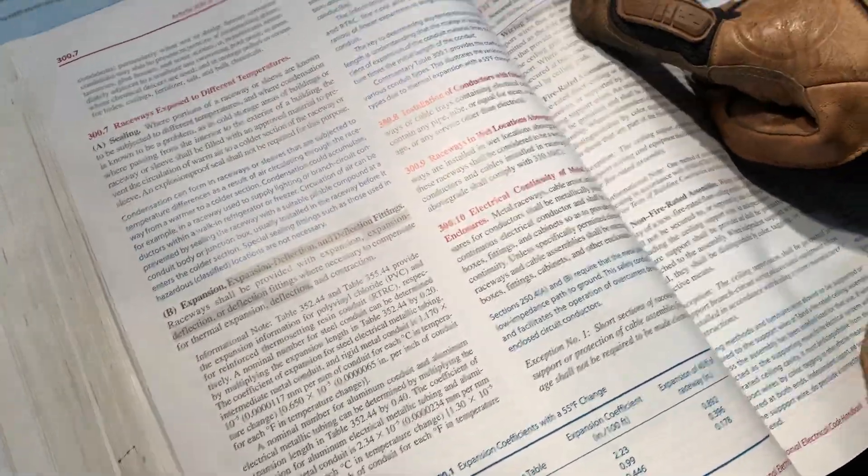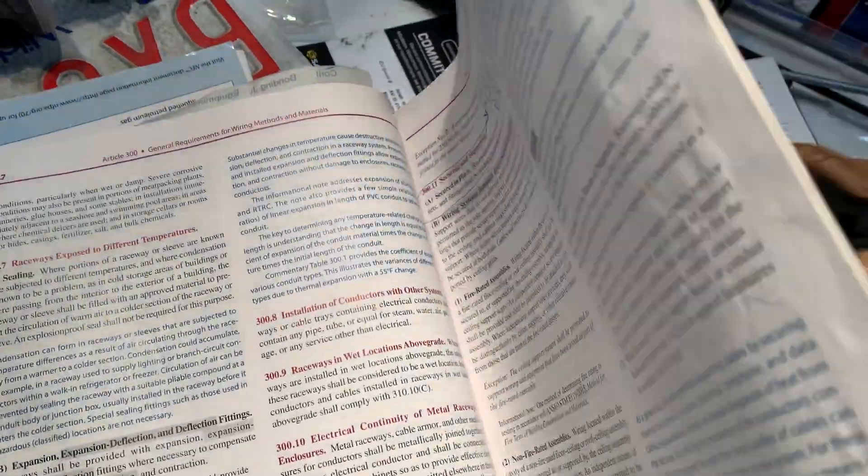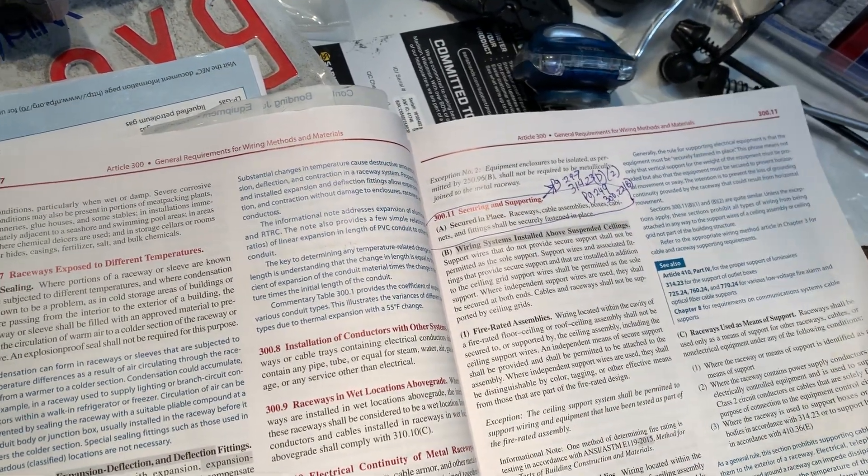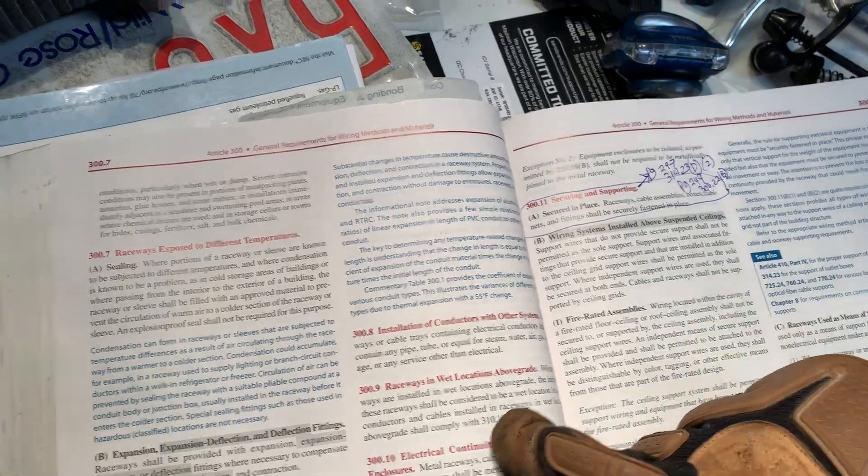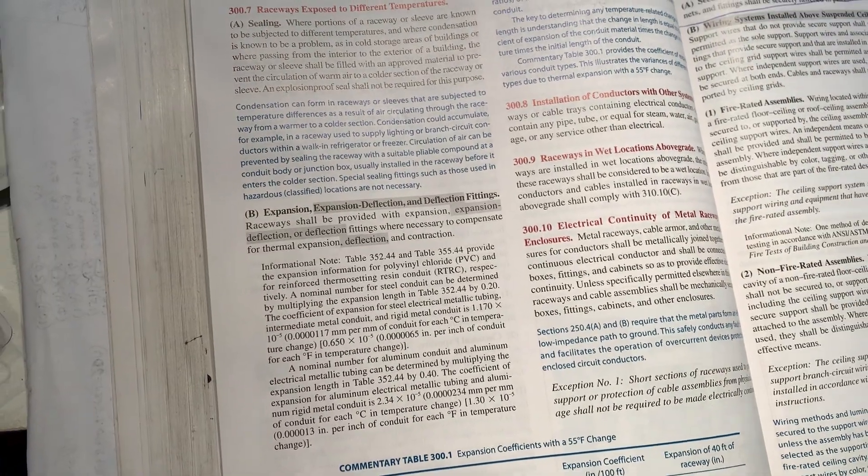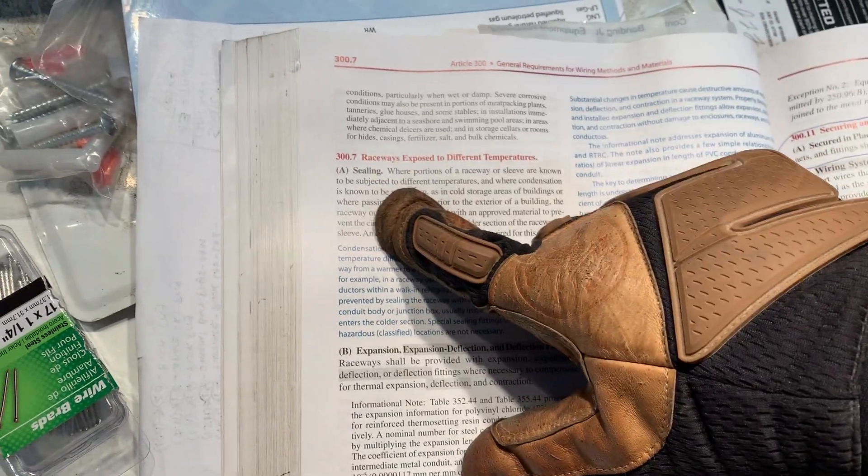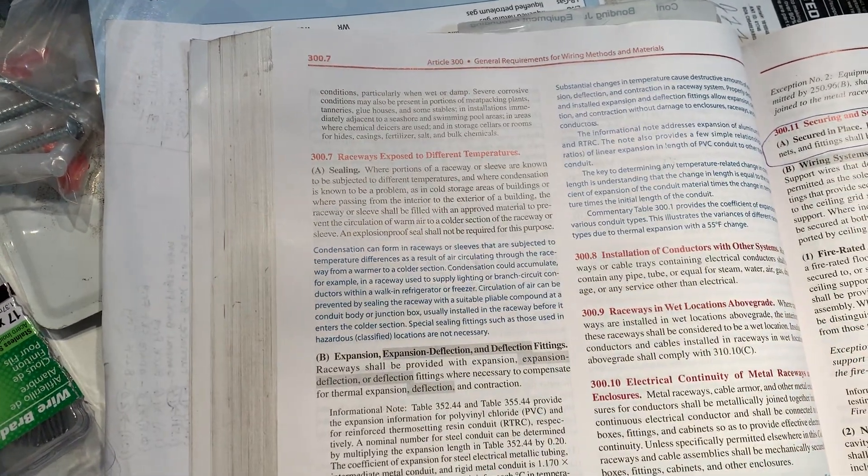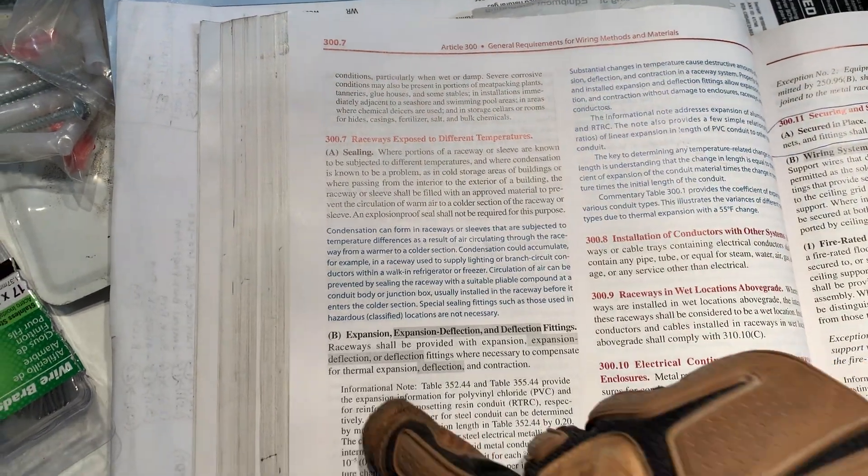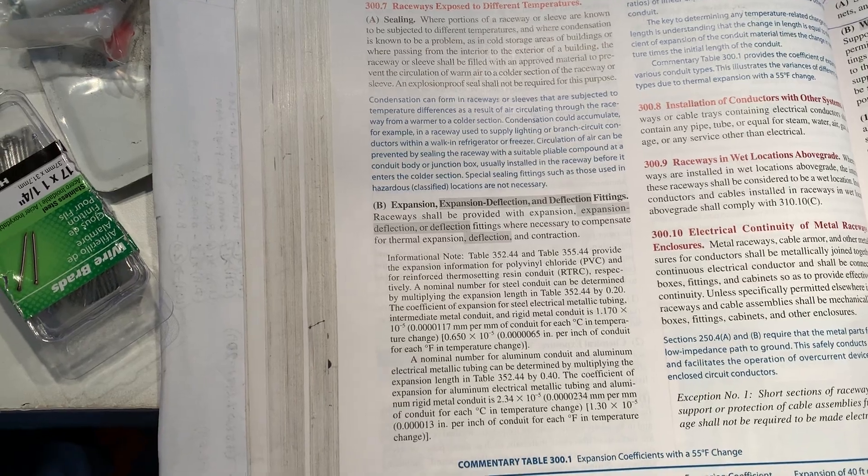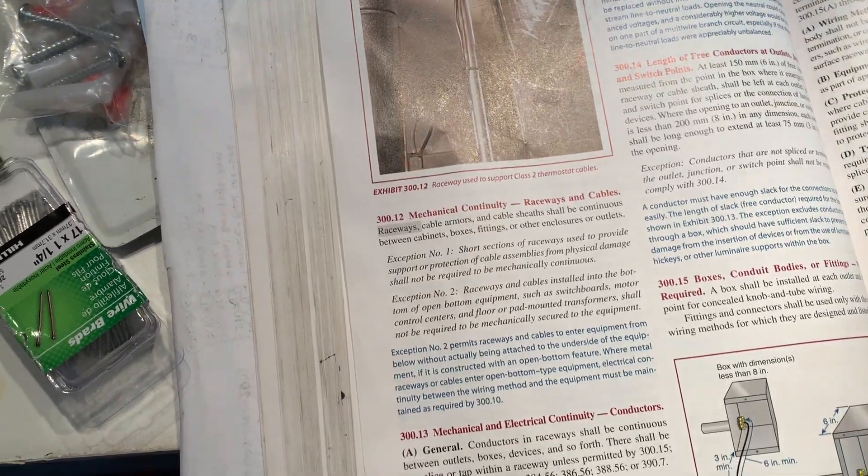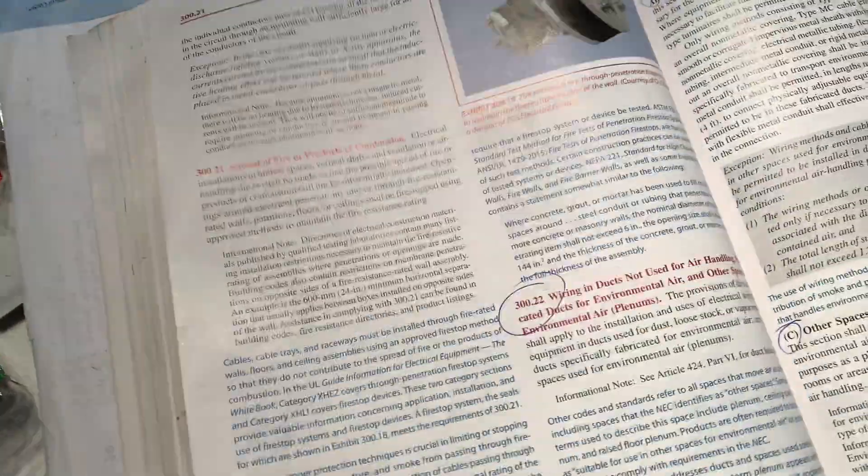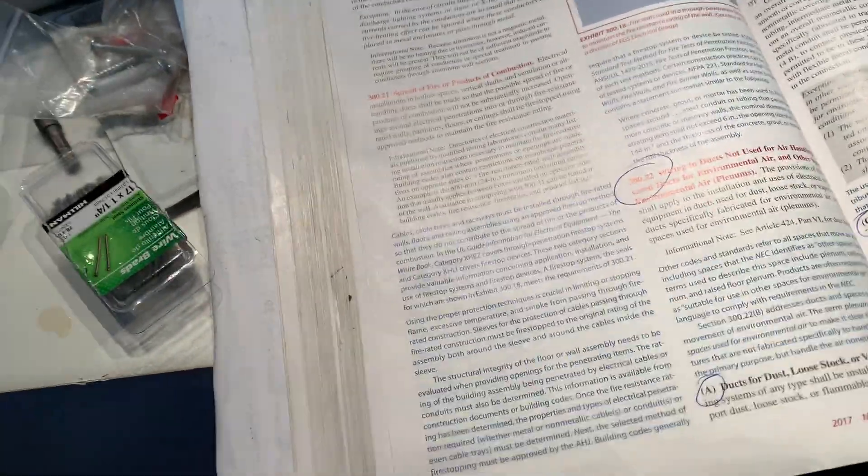Securing and supporting your straps and raceways. I don't agree they did that on the other side, so that might be a number 13 violation I've seen. Above grade, wet locations, you've got to pay attention to 300.9. You're supposed to be sealing your holes, like we said, at the hot tub. Different temperatures, 300.7. Expansion fittings, 300.7B. He didn't have the expansion fittings coming out of the ground, so that's going to pull apart.